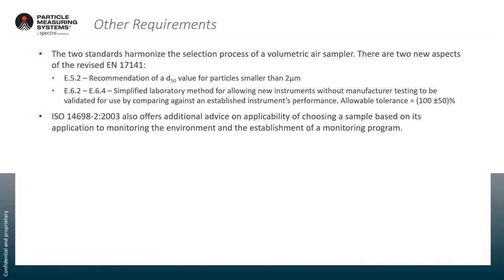The two standards harmonize the selection process of a volumetric air sampler. The new elements in EN 17141 are the D50 requirement for smaller than two microns and the simplified laboratory method. ISO 14698 also offers additional advice on applicability of choosing samplers based on their application to monitor the environment and the establishment of a monitoring program, so there's a little bit of flexibility in technique choice in 14698.